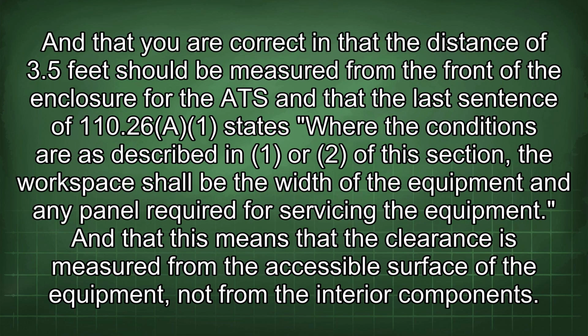And you are correct that the distance of 3.5 feet should be measured from the front of the enclosure for the ATS, and that the last sentence of 110.26(A) states, where the conditions are as described in 1 or 2 of this section, the workspace shall be the width of the equipment and any panel required for servicing the equipment. This means that the clearance is measured from the accessible surface of the equipment, not from the interior components.